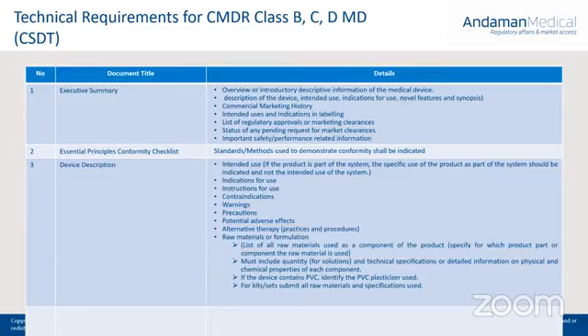One thing that I could share with you on this, please check if your essential principles conformity checklist includes the ISO 13485 standard, because we have some experiences as well that this is being asked by the evaluator and it's being checked and it becomes one of the NODs. So when you receive your essential principles conformity checklist, if the ISO 13485 is not included there, then you have to ask your manufacturer to include that to avoid NODs with FDA.